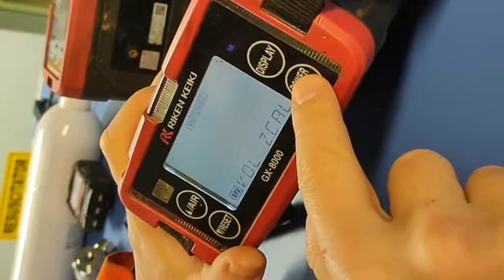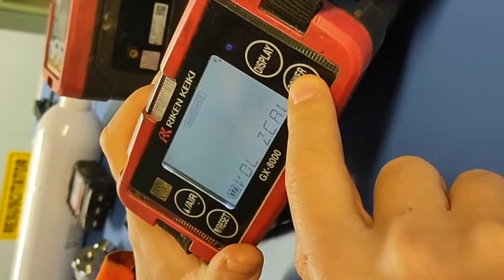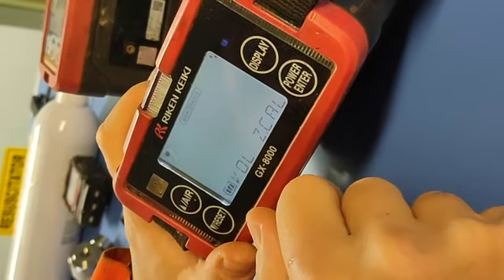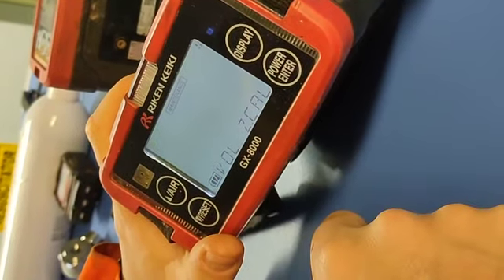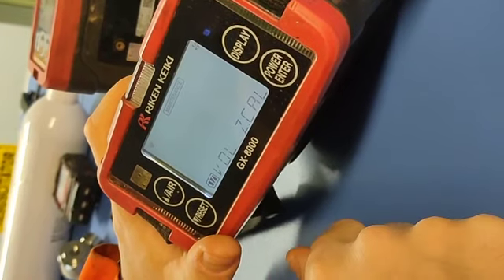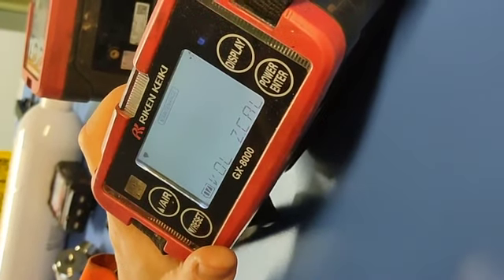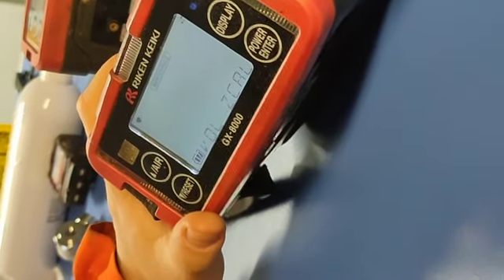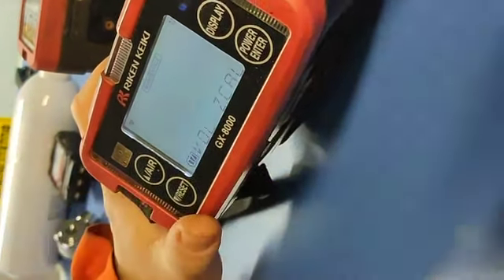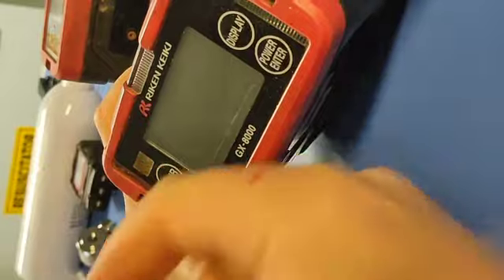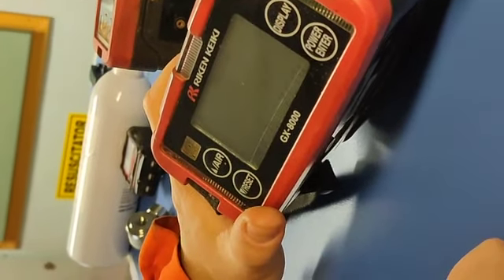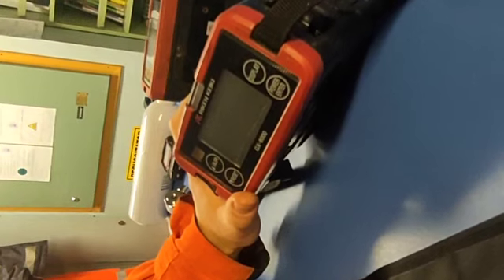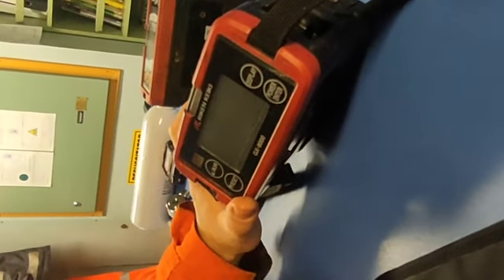This one will zero my sensors which need to be zeroed. For example, hydrogen sulfide is zeroed in the fresh air. The monoxide of carbon is zeroing in the fresh air. The hydrocarbon percentage level is zeroing also in fresh air.